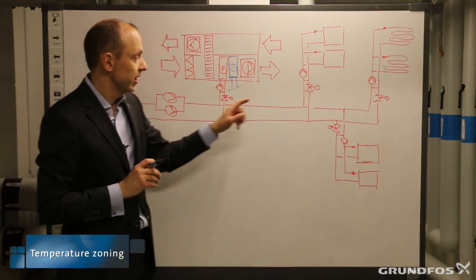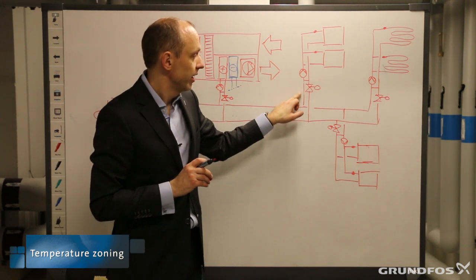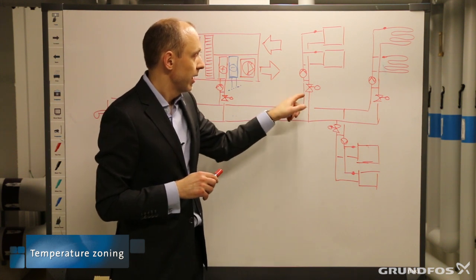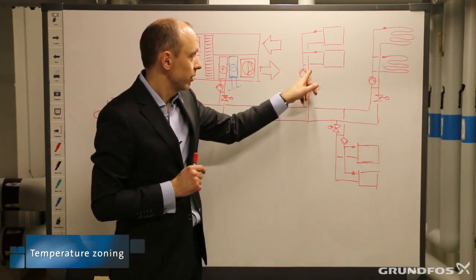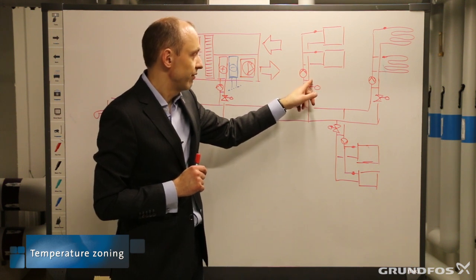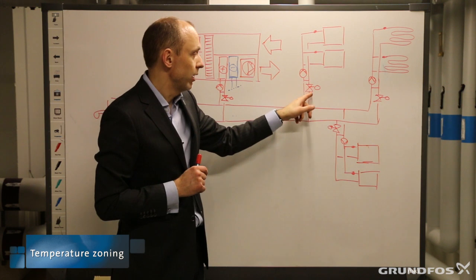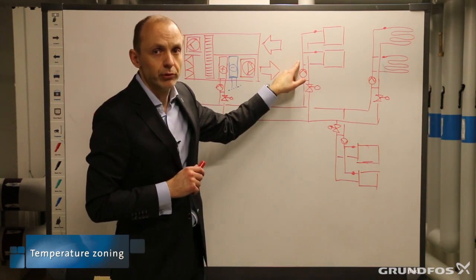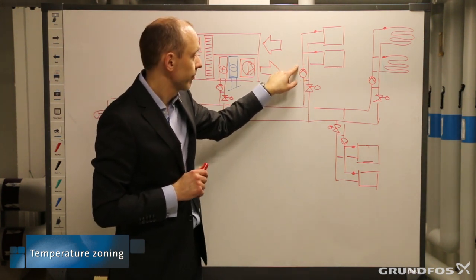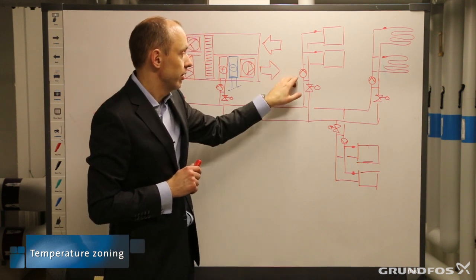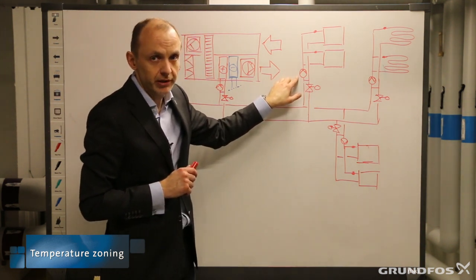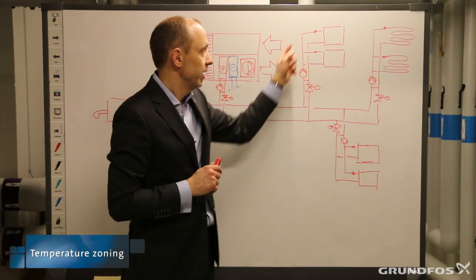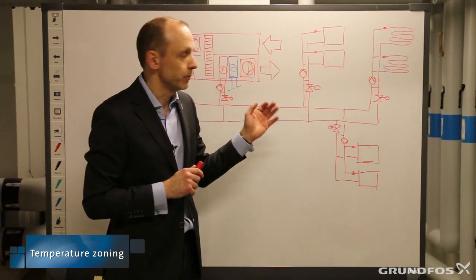The control valve still has the same functionality as before — it still opens and closes according to the performance in the system. But when it closes, some of the chilled or cold water is actually forced back into the flow pipe. So by opening and closing this valve, we can adapt the flow temperature to whatever we would like it to be. We can also run the pump with more or less speed. So now we have a system with both variable flow and variable temperature in the zone.